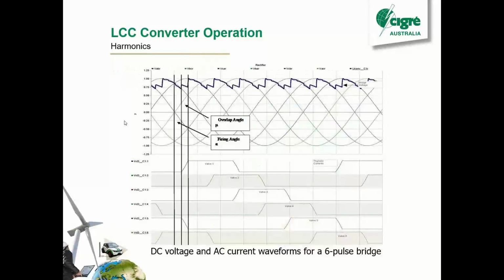So this is just showing you the waveforms for a 6-pulse converter. You can see this is our DC voltage here. We're starting at the peak here, where we've got 2 valves conducting. And then there's a short period here where we've got 3 valves conducting. That's where it's swapping over between the 2. Then we're back to 2 valves conducting. So you've got 2 valves, 3 valves, 2 valves, 3 valves, 2 valves. You can see where we're waiting with our firing angle until we turn that other thyristor on. That's the firing angle alpha, which we talked about, but then there's also this parameter called the overlap angle, and that's the duration of time it takes for the current to swap from one to the other.